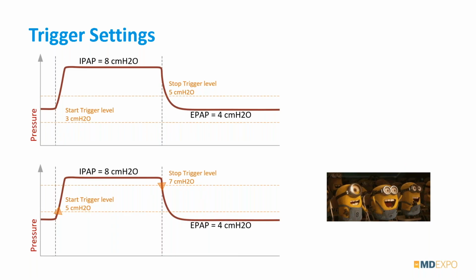So make sure that you familiarize yourself with the trigger settings. Again, in 95% of the situations, you probably don't have to care, but if you have a situation like this, typically BiPAP ventilators, then you will have to adjust your trigger settings accordingly. Otherwise, you'll not be able to measure these parameters. Any questions about trigger settings?